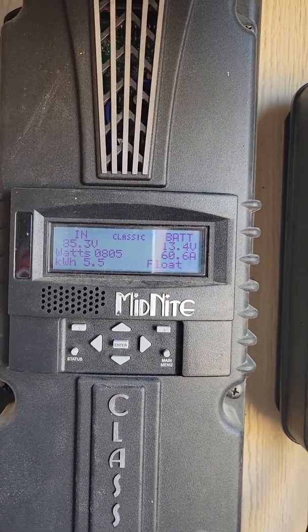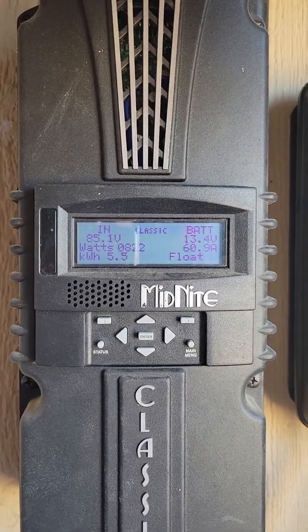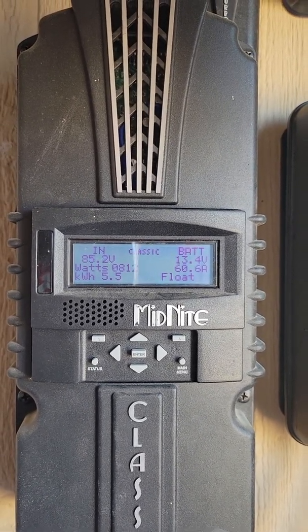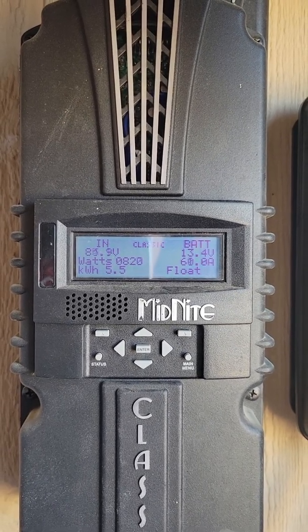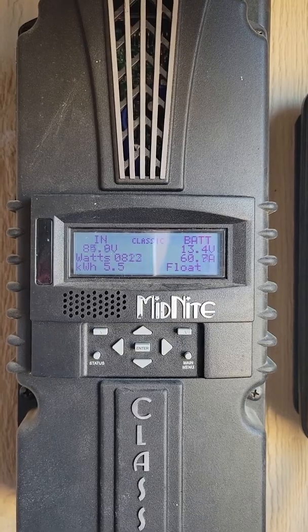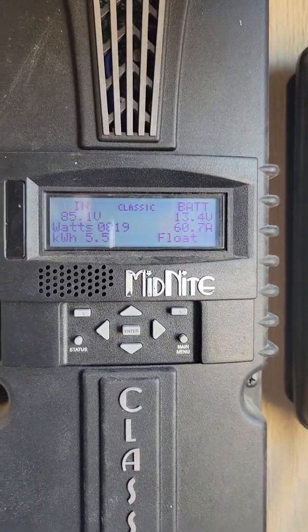That's what I should be getting anyway, because I have two strings with all those panels broken down — coming in at about 915 watts each, so that would be 1,830 total. I think the two strings themselves are also limiting. But as you can see, I've also got 60 amps coming in.